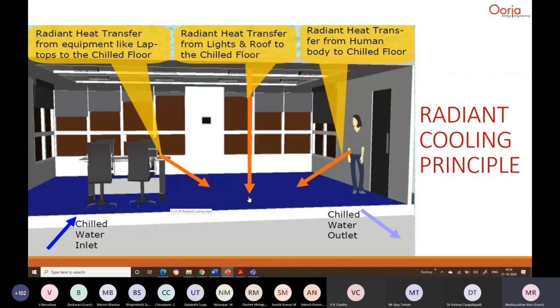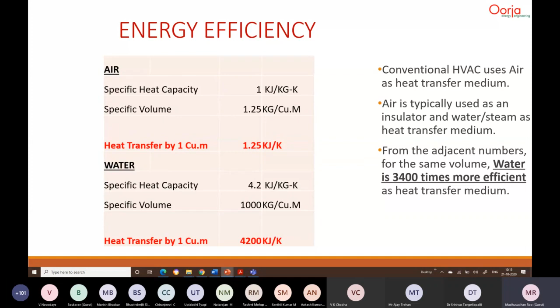And why is there better efficiency? If you're using air as a means of heat transport, which is what we do in air conditioning, 1 cubic meter of air can do only 1.25 kilojoules of heat transfer per degree change in temperature. That's because of its specific heat and specific volume. But 1 cubic meter of water can do close to 4,200 kilojoules of heat transfer per degree change in temperature.